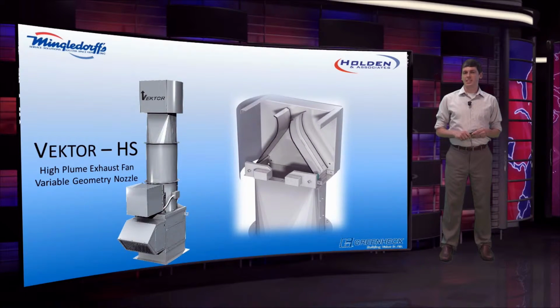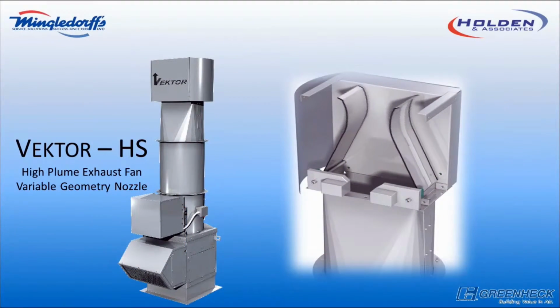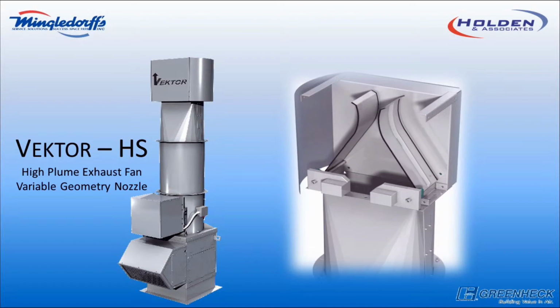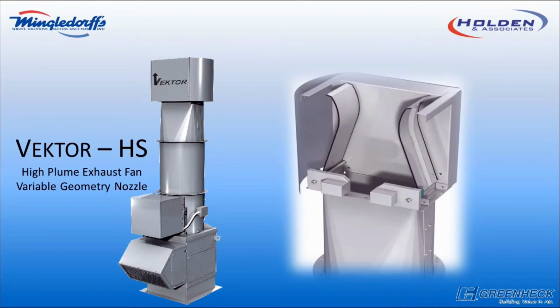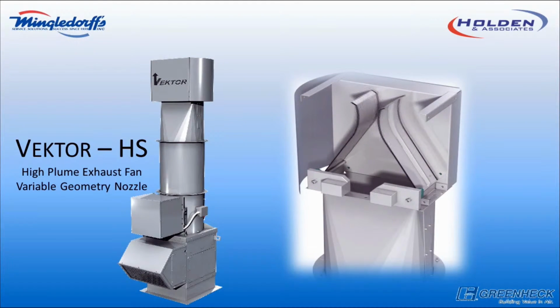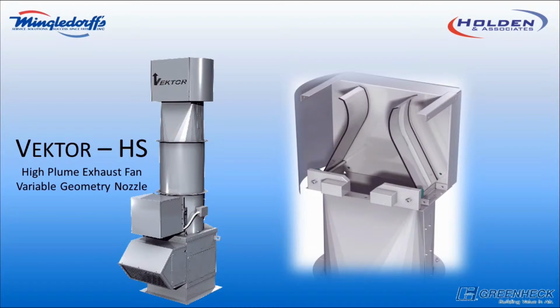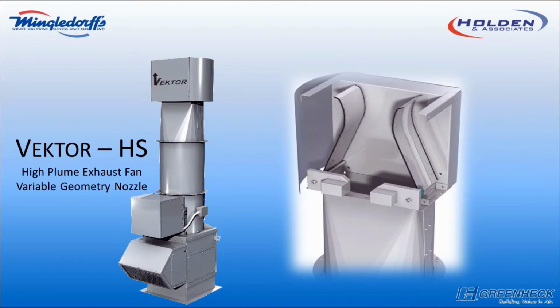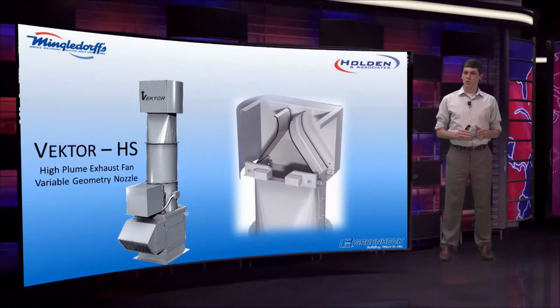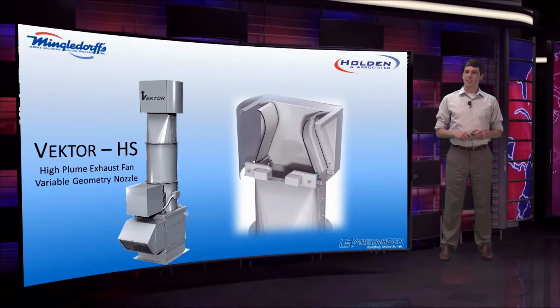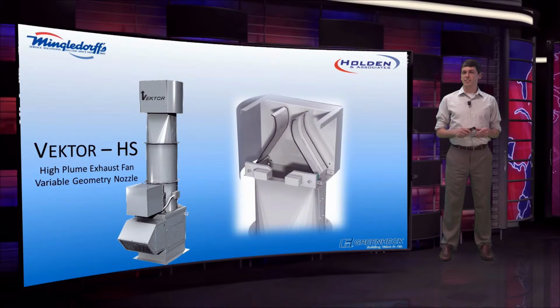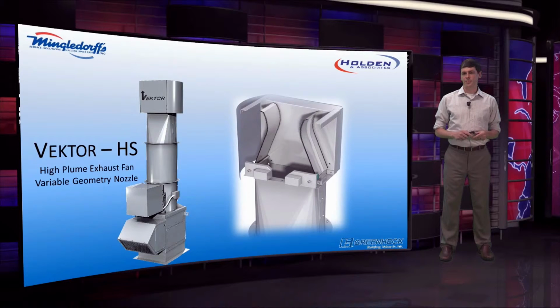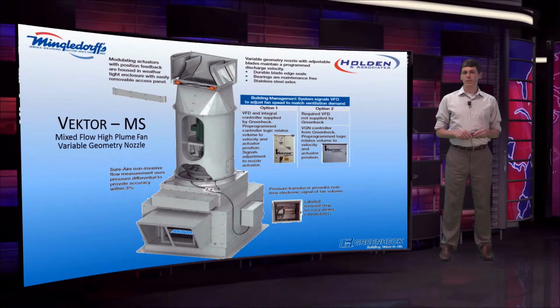Now we're going to talk in more detail about the variable geometry nozzle. As you can see on the screen, the blades modulate, open and closed, and will do this based on the demand of the space. In applications where less exhaust is needed, the fan motor will slow down, the blades will close, decreasing the cross-sectional area, allowing the system to maintain a 3,000 feet per minute discharge. Shown here is the Vektor MS system.